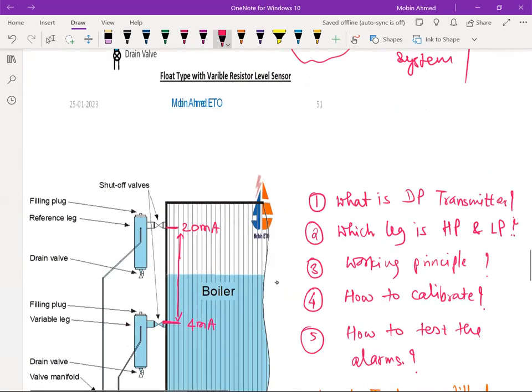And when the water level is at the normal water level, NW, you can see it in the level gauge. If the water level is NW, and you have done this adjustment correctly, it's supposed to read 12 milliampere. Okay, it's supposed to read 12 milliampere. So this is how we do the calibration.